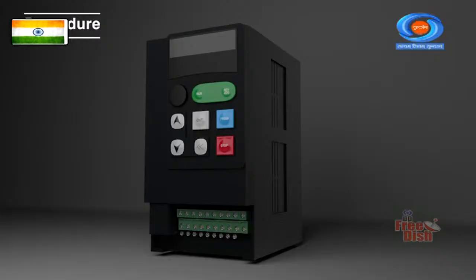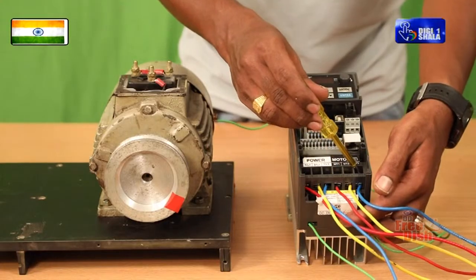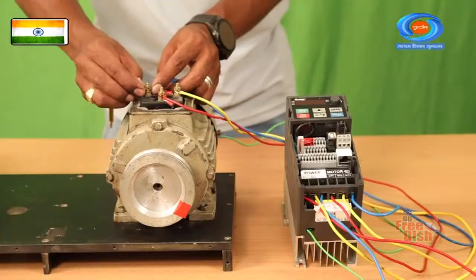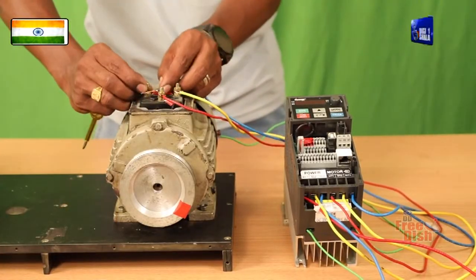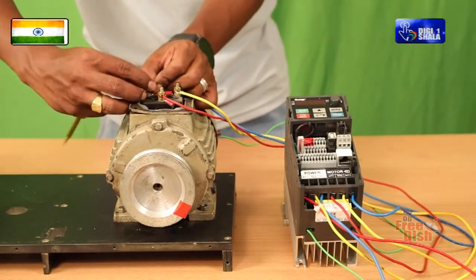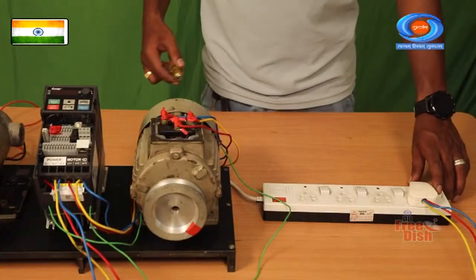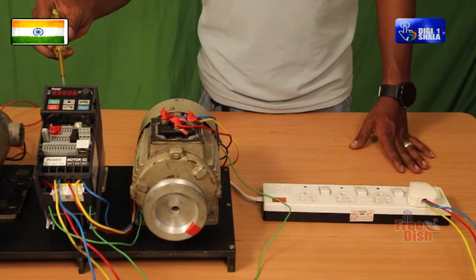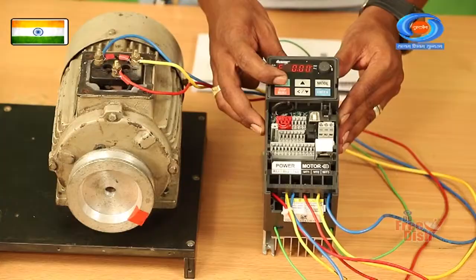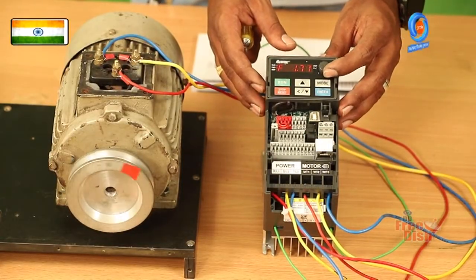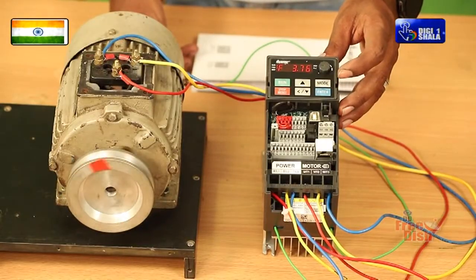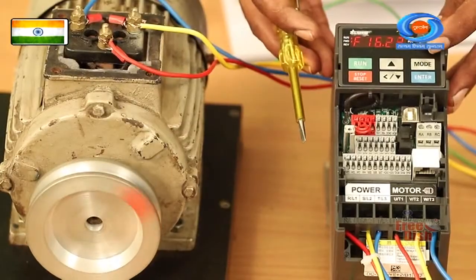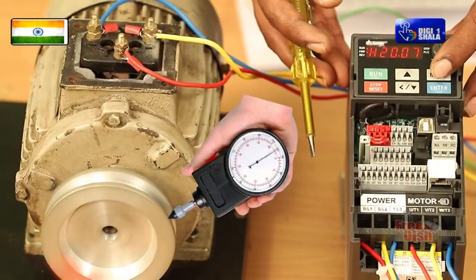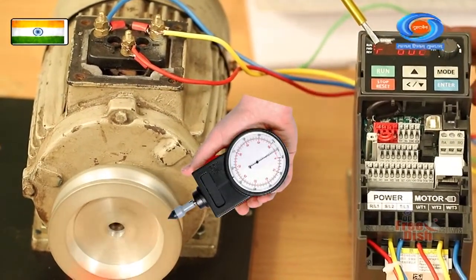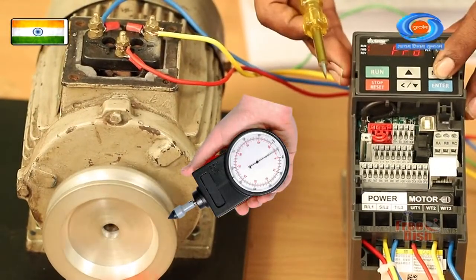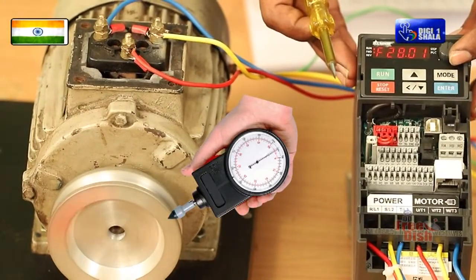Select the suitable type of model AC drive. Connect and wire the AC drive input power supply with terminals RL1, SL2, TL3, while the output terminals UT1, VT2, WT3 are connected to the motor. Switch on the power supply main. Press the run or stop button. The motor will run. Measure the speed of the motor by using the tachometer and record it in RPM, revolutions per minute. Increase and decrease the frequency and check the change in speed of the motor.